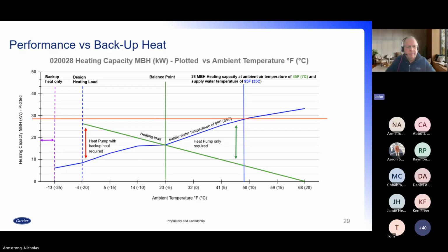So what this graph is representing is the balance point. So we've interjected here a heat load in the system, which is about 26,000 BTUs. And you can see as we move on the right-hand side of that graph, the heat pump is going to satisfy the temperature for that particular building right up to about that 23-degree Fahrenheit point. And after that point, the heat pump is going to start to struggle to heat. So now we need to find out when do we need to bring in our backup heat. And that's the point where we'd be looking.